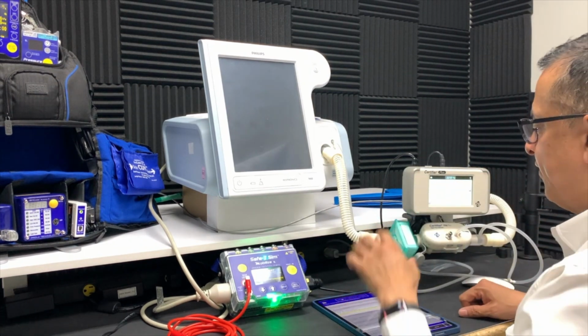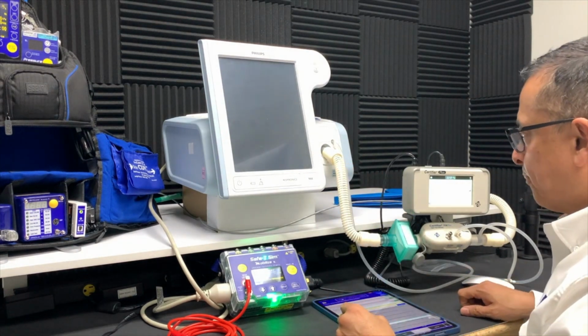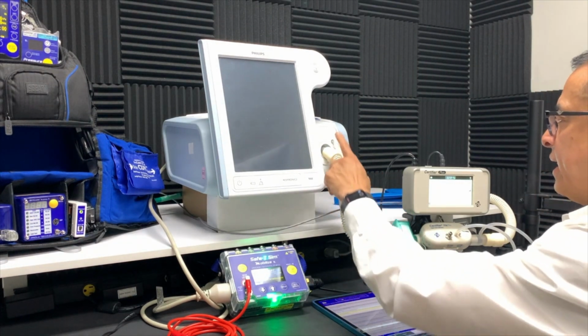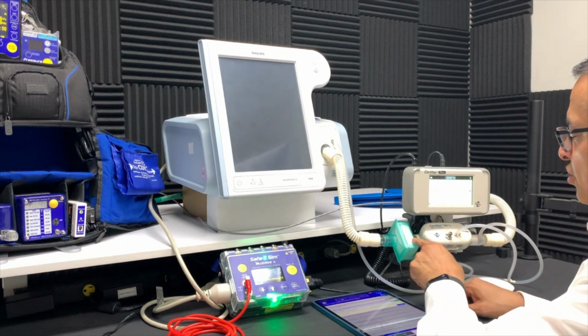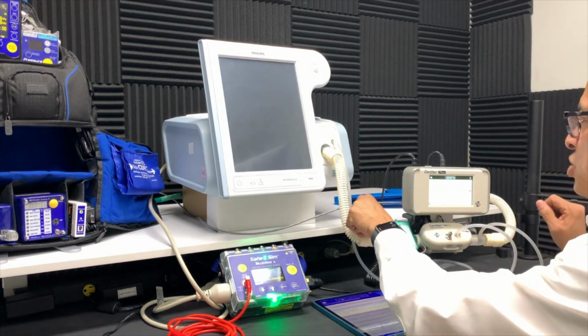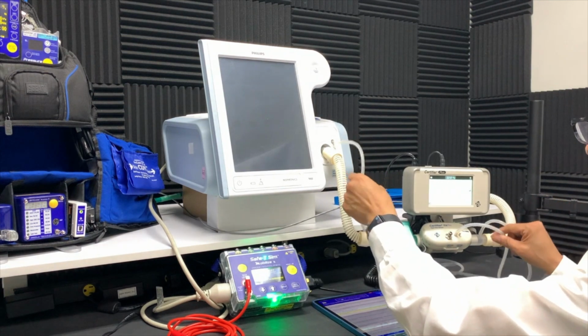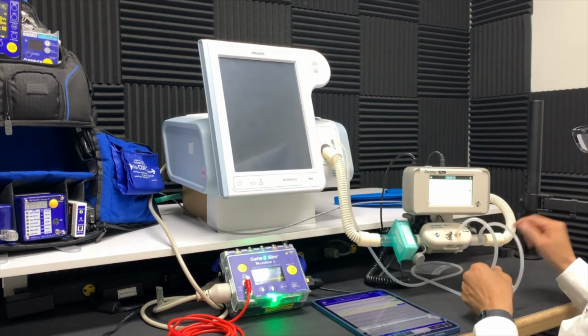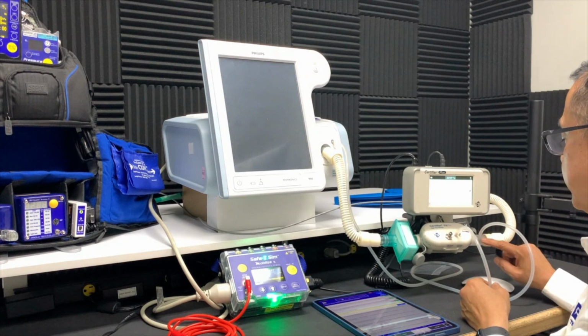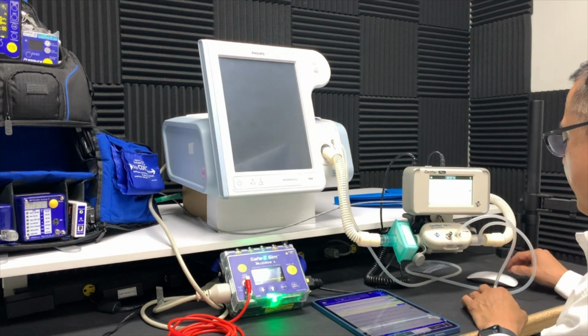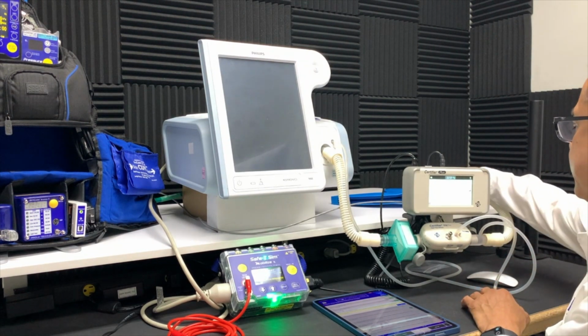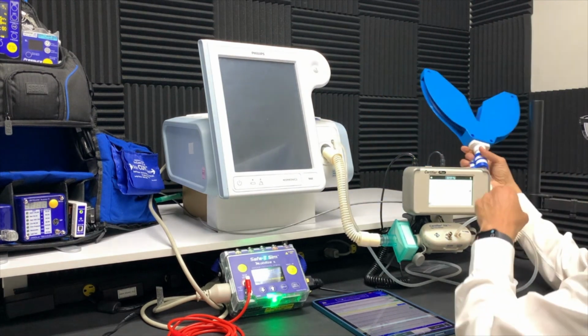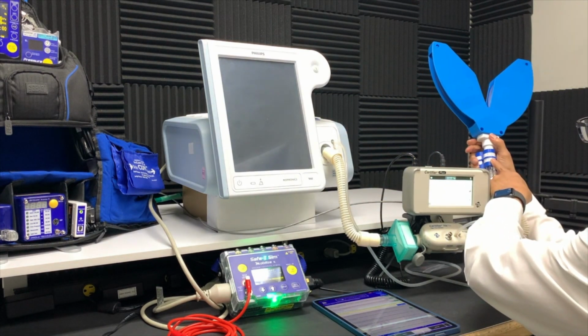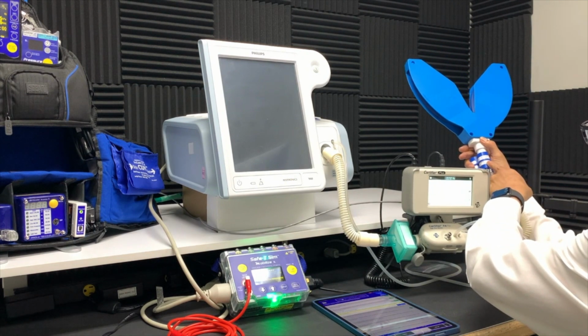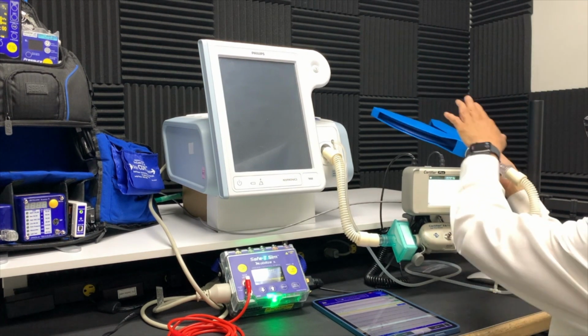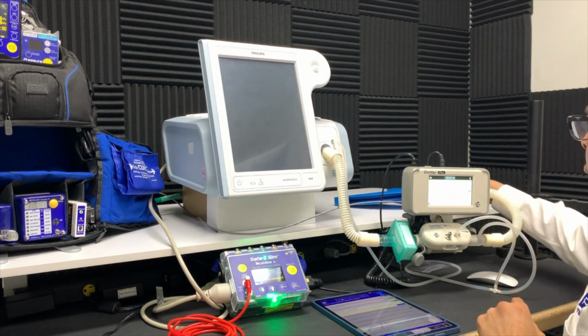For these tests, we need to configure our analyzer properly by connecting the output over into our tubing here, through our filter, into the flow meter, making sure we're connecting our proximal pressure port into our analyzer as well, and also connecting a pickoff port on the output so that we can measure that pressure. And now we want to connect the output hose to a resistance set at a value of 20 centimeters of H2O connected to our test lung.